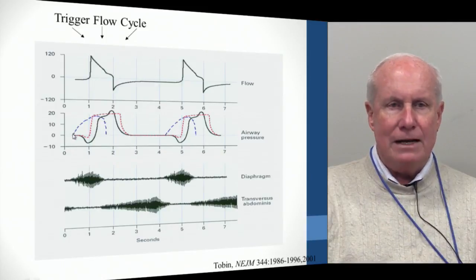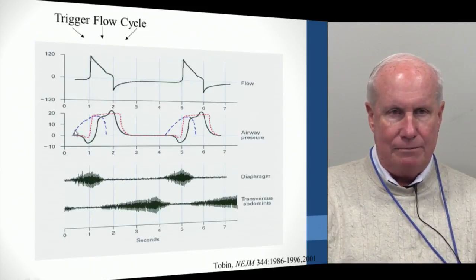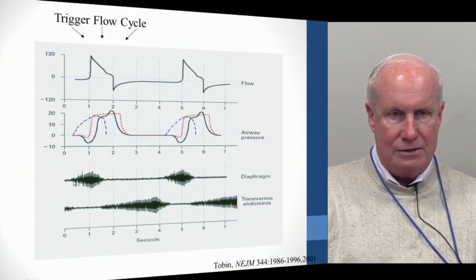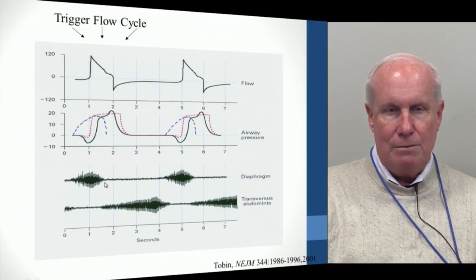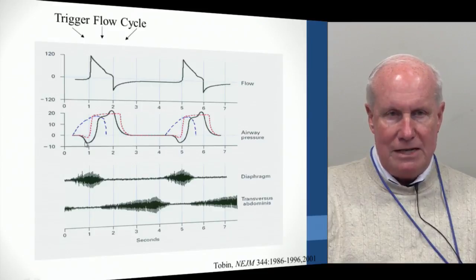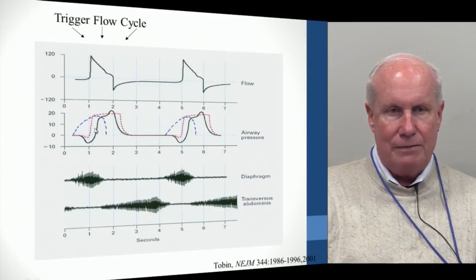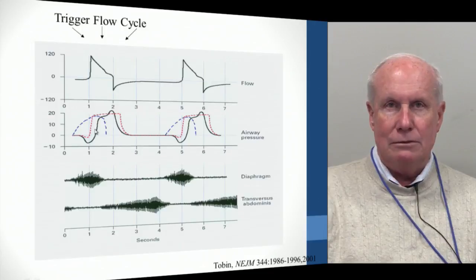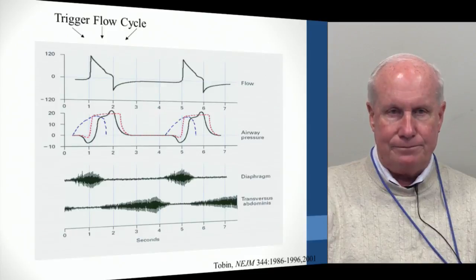And what you want your ventilator to do is follow this little dotted blue line right there. So you want the pressure to rise as the patient effort begins. You want the pressure to peak when the effort is at its greatest. And you want the pressure to fall when the patient effort ceases, right? This is not always easy to do. And oftentimes on ventilators, if you look carefully, you can see these big negative swings in the airway pressure, indicating the patient is flow starved. The pressure and the flow are not keeping up with the patient's effort.